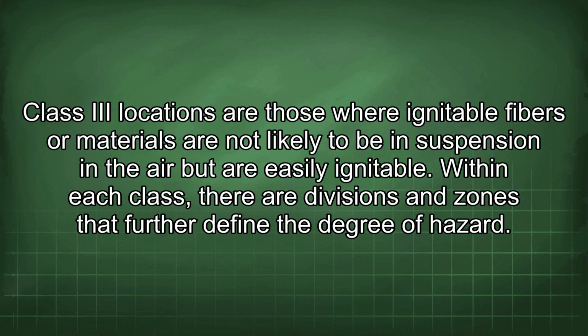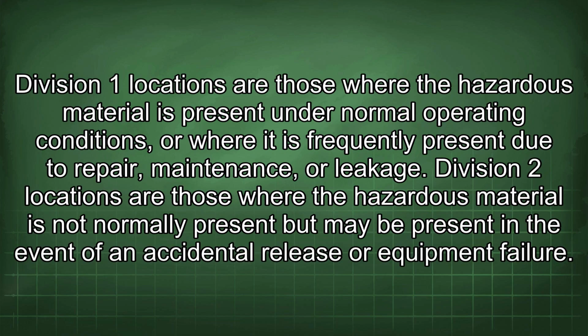Within each class, there are divisions and zones that further define the degree of hazard. Division 1 locations are those where the hazardous material is present under normal operating conditions, or where it is frequently present due to repair, maintenance, or leakage. Division 2 locations are those where the hazardous material is not normally present but may be present in the event of an accidental release or equipment failure.